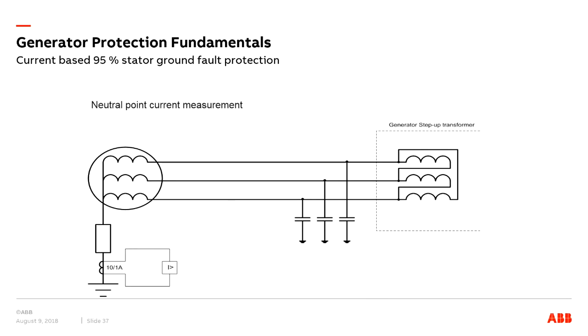So as I mentioned, the other way of detecting a stator ground fault is by measuring the neutral current. The current measurement in the neutral point is equivalent to the neutral point voltage measurement, as we can see here. So, excuse me, the neutral CT will measure the ground fault current, and we can make it work. This is typically called a 95% stator ground fault protection, and we will see in the upcoming slide why it is 95%.